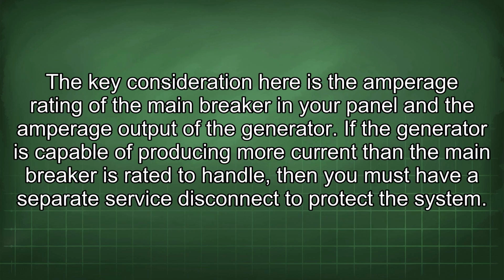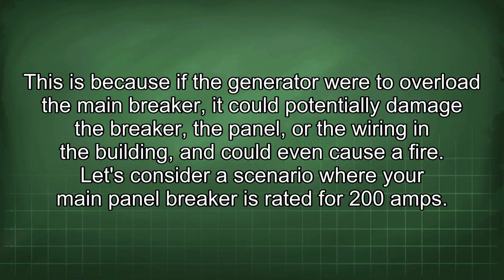The key consideration here is the amperage rating of the main breaker in your panel and the amperage output of the generator. If the generator is capable of producing more current than the main breaker is rated to handle, then you must have a separate service disconnect to protect the system. This is because if the generator were to overload the main breaker, it could potentially damage the breaker, the panel, or the wiring in the building, and could even cause a fire.